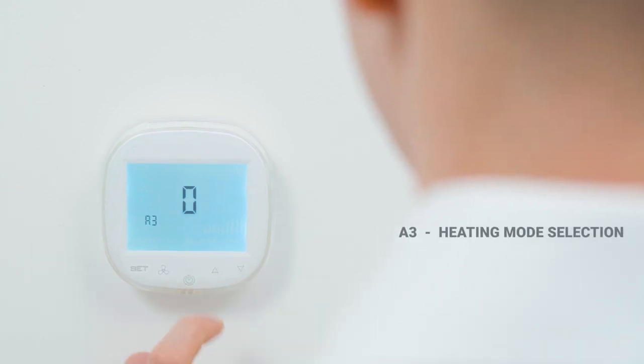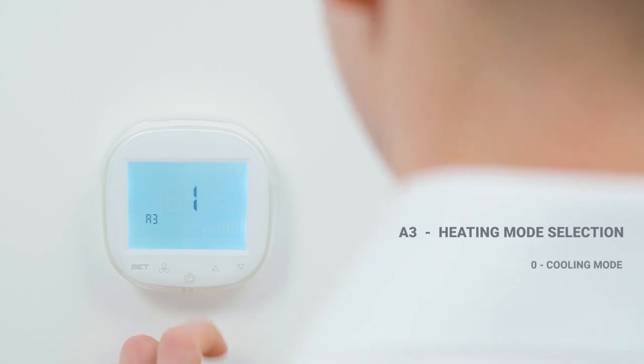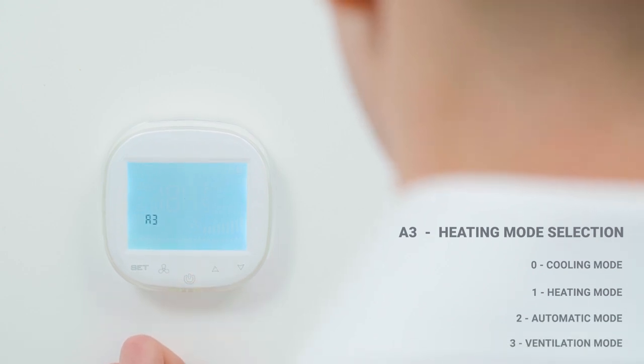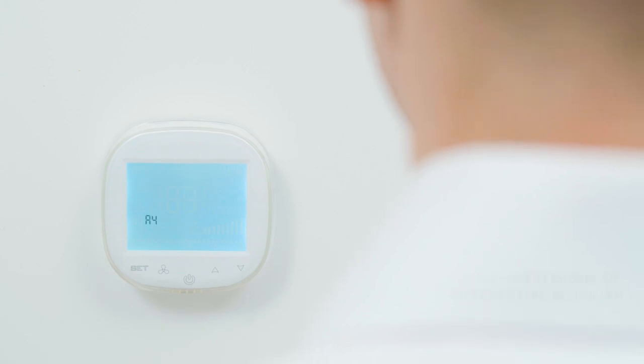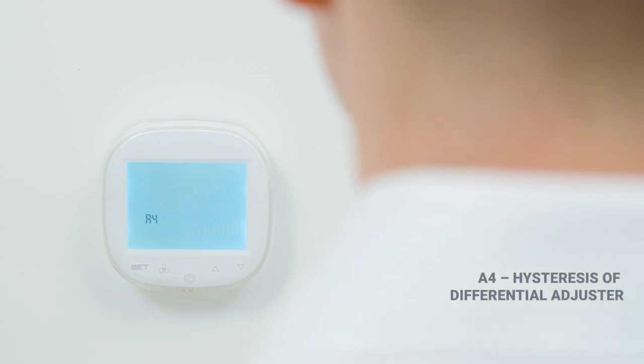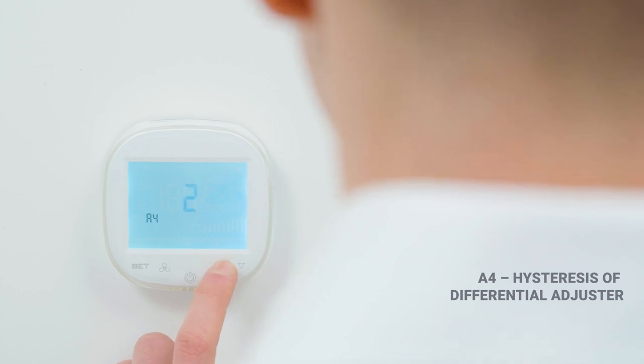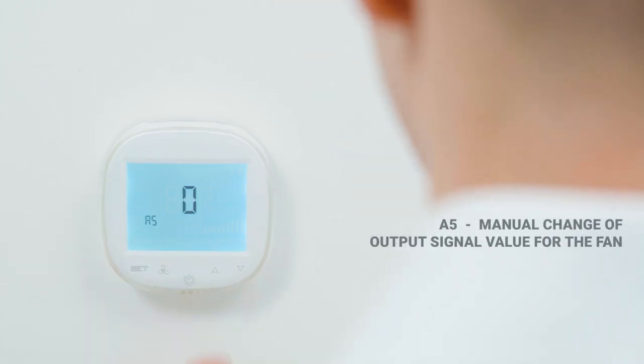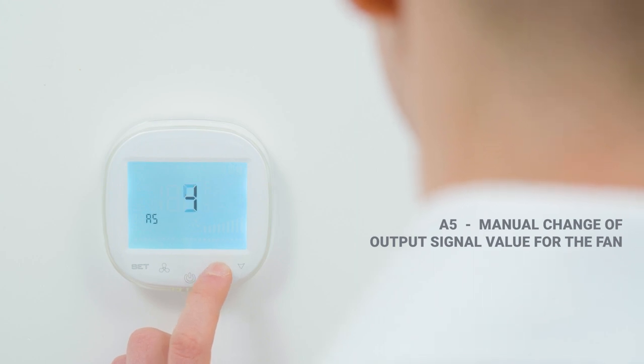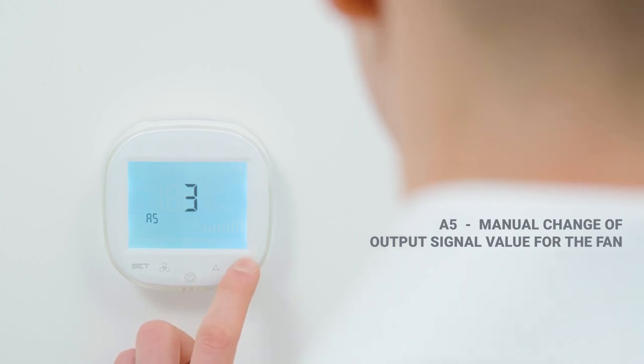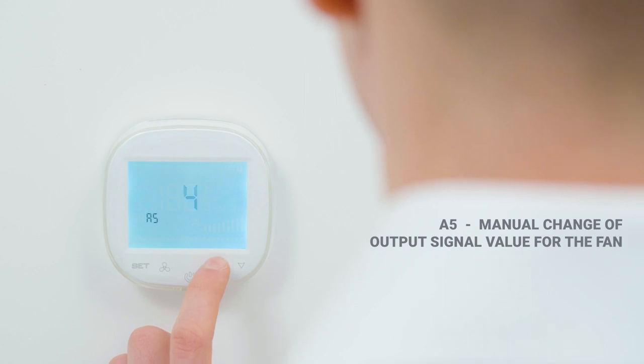Function A3, heating mode selection. Value 0 means cooling mode, value 1 means heating mode, value 2 means automatic mode, and value 3 means ventilation mode. Function A4, controller hysteresis setting. This is the difference between the set point temperature and the room temperature, followed by switching on the device. Function A5 allows us to increase the value of the output signal. For example, when in automatic mode the set point temperature is not reached, we have a possibility to increase the value of the output signal. In practice, this forces a higher fan speed in automatic mode.